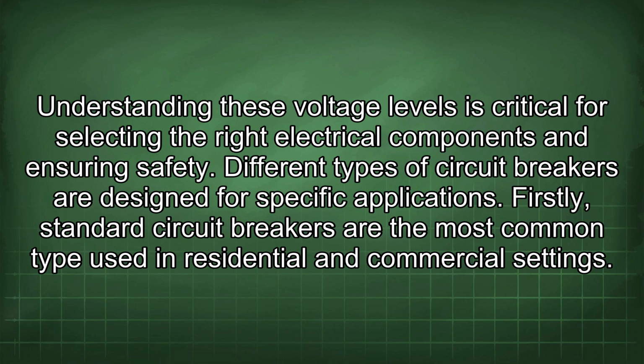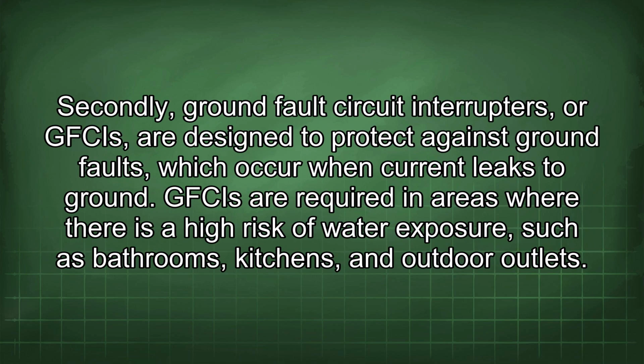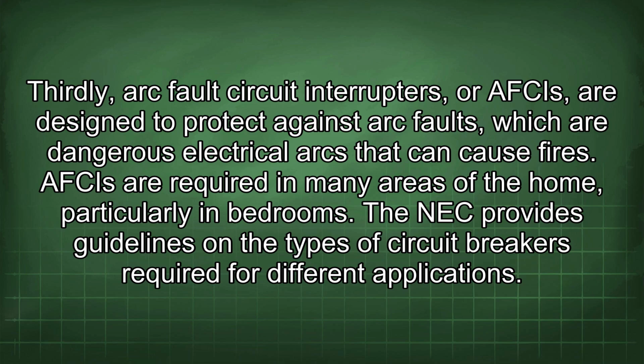Different types of circuit breakers are designed for specific applications. Firstly, standard circuit breakers are the most common type used in residential and commercial settings. Secondly, ground fault circuit interrupters, or GFCIs, are designed to protect against ground faults, which occur when current leaks to ground. GFCIs are required in areas where there is a high risk of water exposure, such as bathrooms, kitchens, and outdoor outlets. Thirdly, arc fault circuit interrupters, or AFCIs, are designed to protect against arc faults, which are dangerous electrical arcs that can cause fires. AFCIs are required in many areas of the home, particularly in bedrooms.